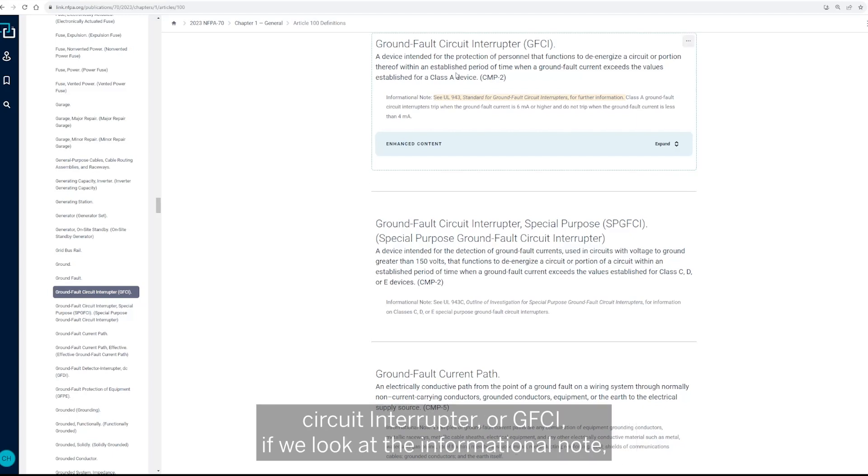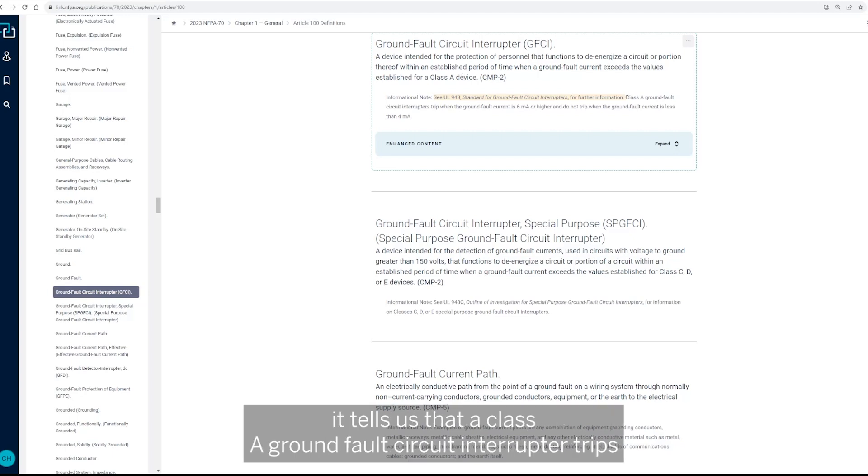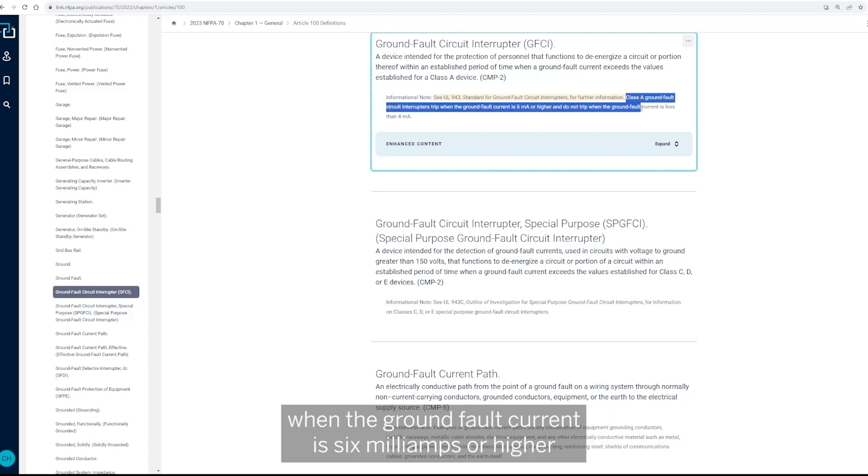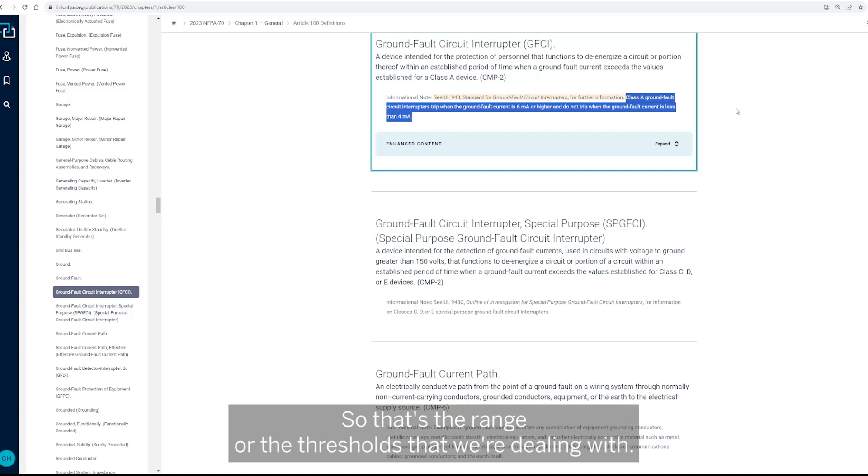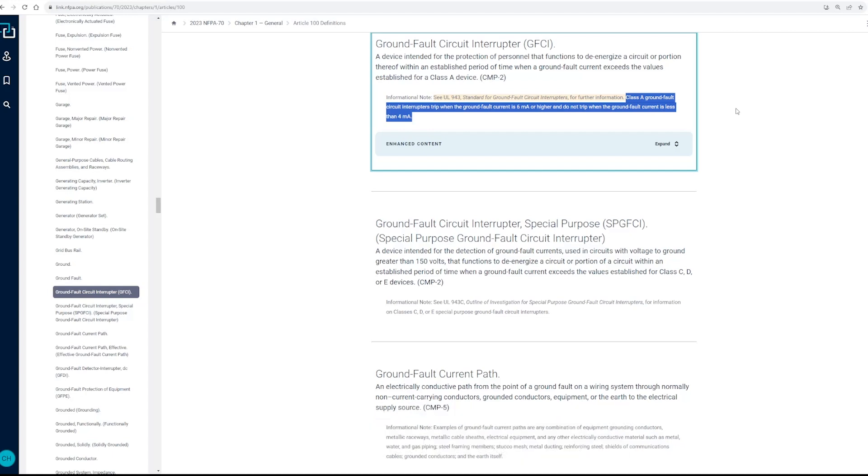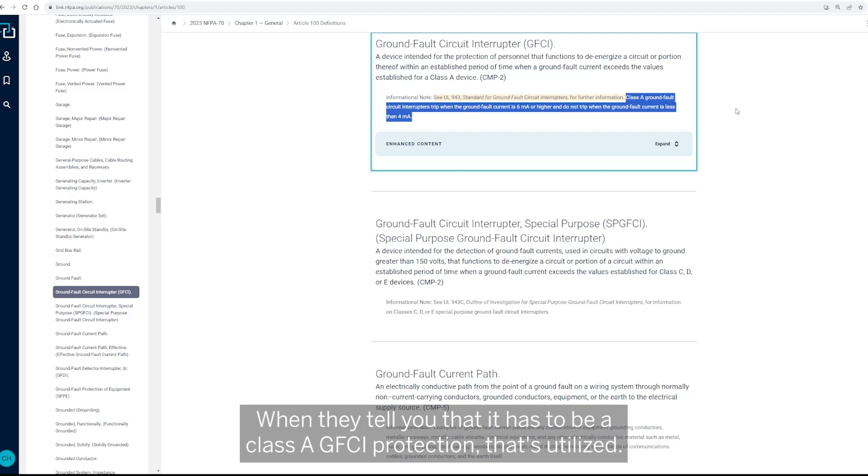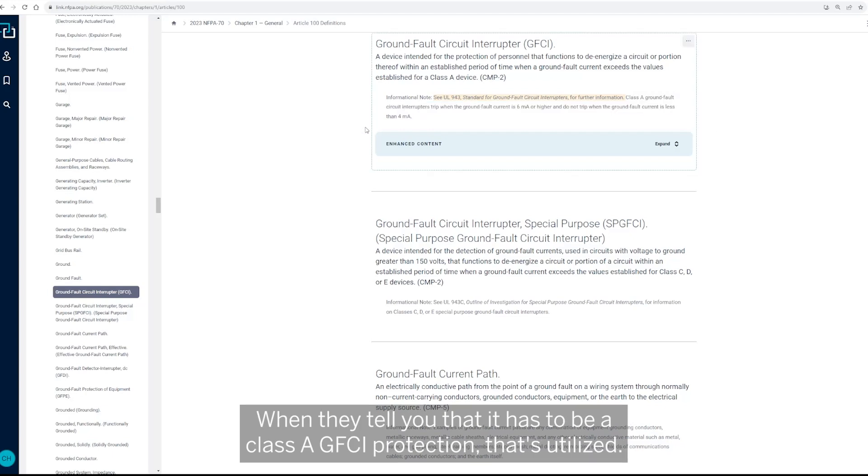If we look at the informational note, it tells us that a Class A ground fault circuit interrupter trips when the ground fault current is six milliamps or higher and does not trip when the ground fault current is less than four milliamps. So that's the range or the thresholds that we're dealing with when they tell you that it has to be a Class A GFCI protection that's utilized.